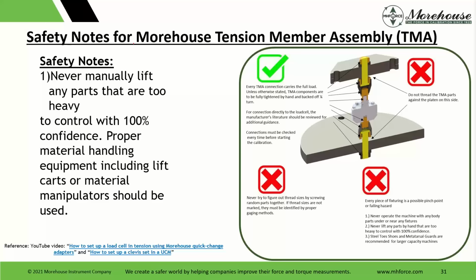Other safety notes: never manually lift any parts that are too heavy to control with 100% confidence. Proper material handling equipment, including lift carts or material manipulators, should be used. And then we have this YouTube video on how to set up a tension using our quick change, and how to set up in a UCM. But every TMA, tension member adapter, that's what TMA is, connection carries the full load unless otherwise stated. TMA components are to be fully tightened by hand and backed off about a quarter turn. That's what we're saying here. For connection directly to the load cell, manufacturer's literature should be reviewed for additional guidance, and connections must be checked every time before starting the calibration.